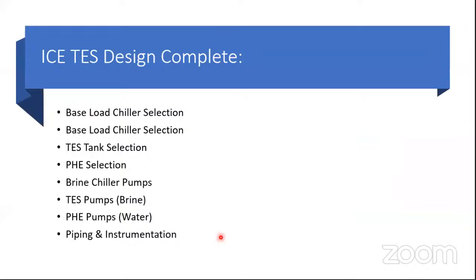So that nearly completes our ice thermal storage design. Also, we have selected the base load chiller. Pardon me, it should be the brine chiller here. We have selected our brine chiller. We have done the thermal storage tank selection also. We have done our PHE selection also. We have done our brine chiller pumps also. And there are TES pumps also that we have selected for the corresponding load it is bearing. And we have selected our PHE pumps also for the water side. That would anyway be like a primary pump for the base load chiller. And then there will be piping and desired instrumentation, which will together constitute the ice thermal storage system.